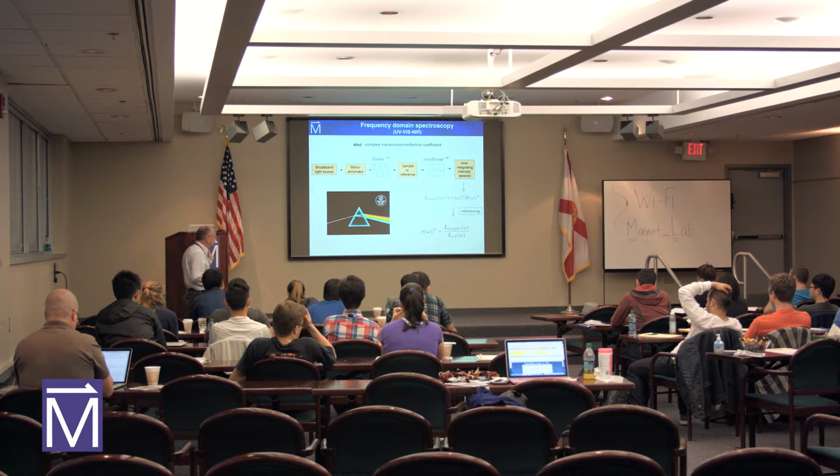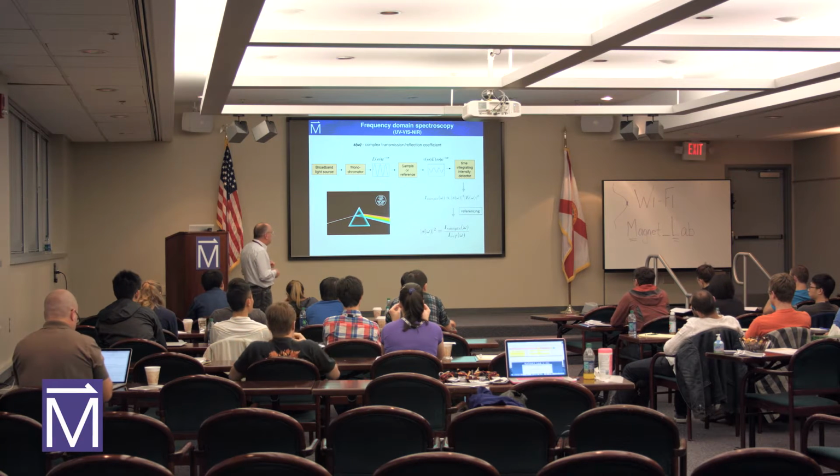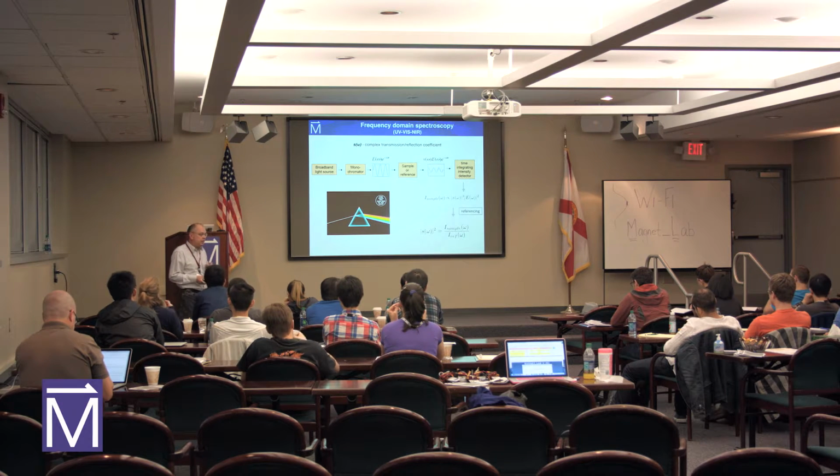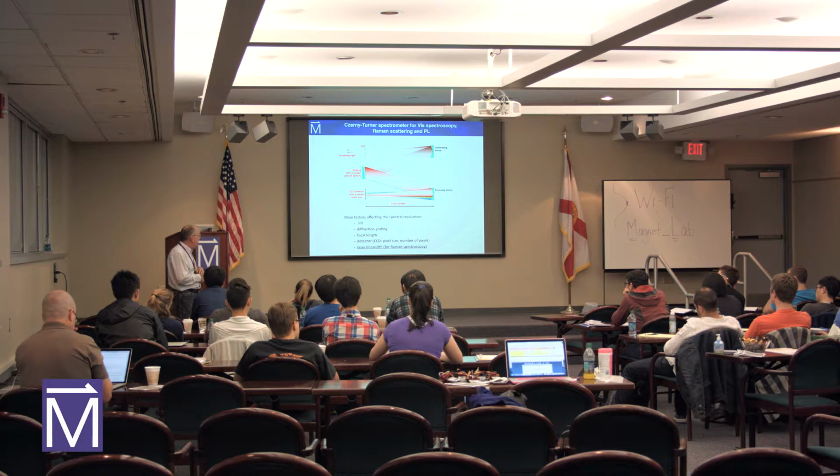It can be realized in different ways. For example, we can remove the actual monochromator here and use a spatially resolved detector, like a so-called CCD camera. Something like this. This is the layout of a Czerny-Turner spectrometer. Incoming light comes through the slit. That's the first important thing to determine your spectral resolution. And then it goes not to a prism. Prism absorbs a lot. It's not easy to operate. To the grating that disperses light, and then it's a multi-pixel detector. By addressing a particular pixel, one can say, okay, this is that energy, and that energy.